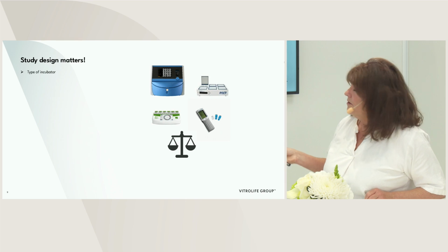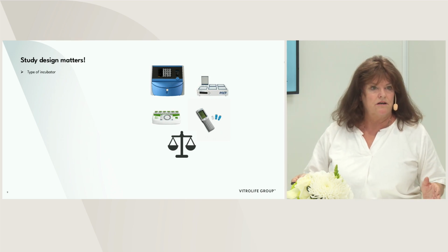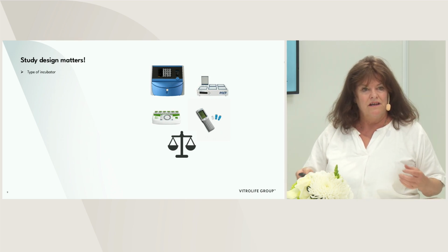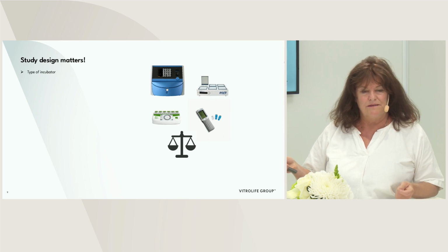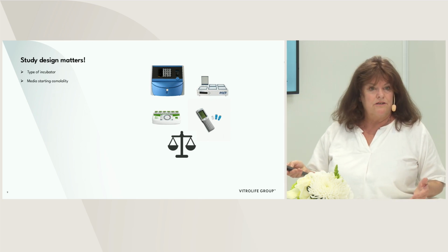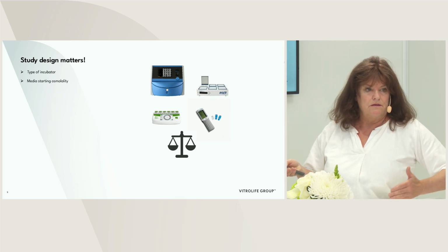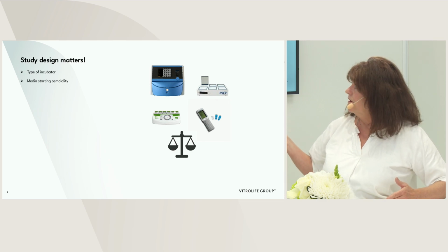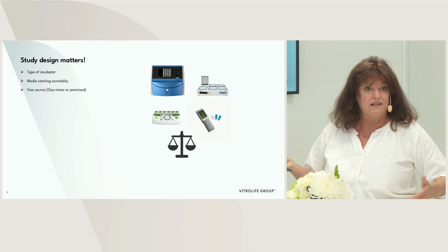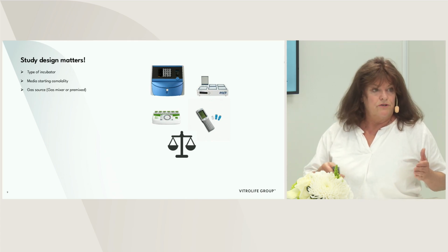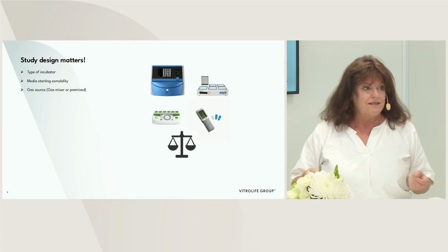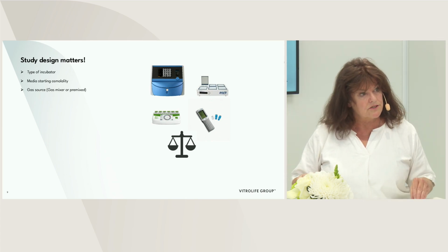So we see so many studies out there saying dry and non-dry, but these studies sometimes are lacking information. The type of incubator you're using, are you using truly a benchtop incubator? What was the starting osmolality of the media? The gas source, if it's a premix gas, that is dry, versus if it's a gas mixer incubator.